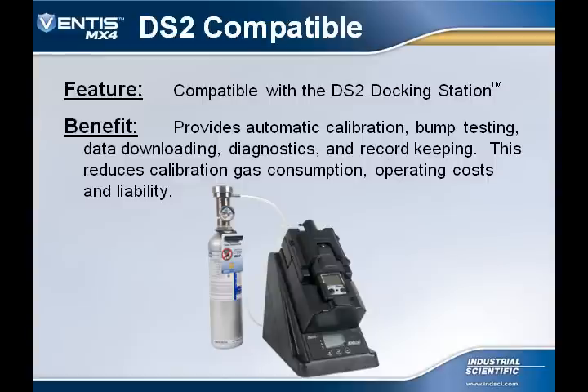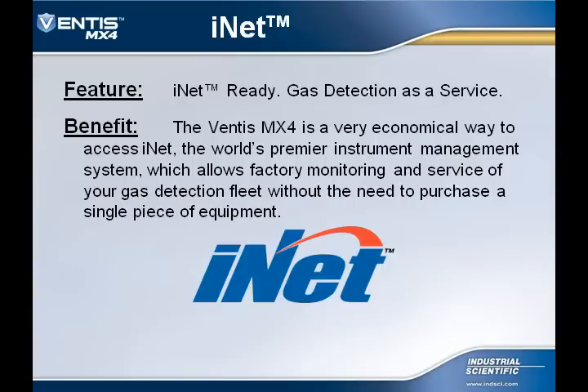The Ventis MX4 is compatible with the DS2 docking station. The DS2 docking station provides automatic calibration, bump testing, data downloading, diagnosing, and record keeping, thus reducing calibration gas consumption, operating costs, and liability. The Ventis MX4 is an economical way to access iNet, a premier gas detection management system. iNet allows factory monitoring and service of your gas detection fleet without the need to purchase a single piece of gas detection equipment.